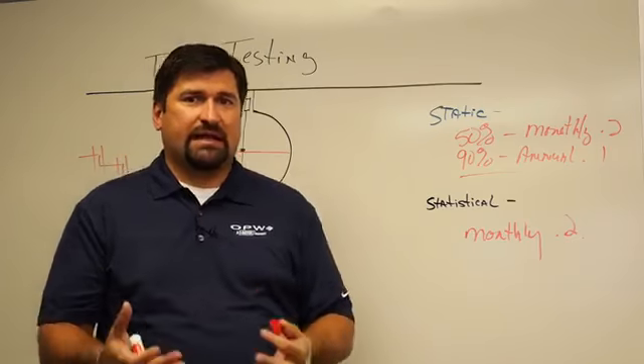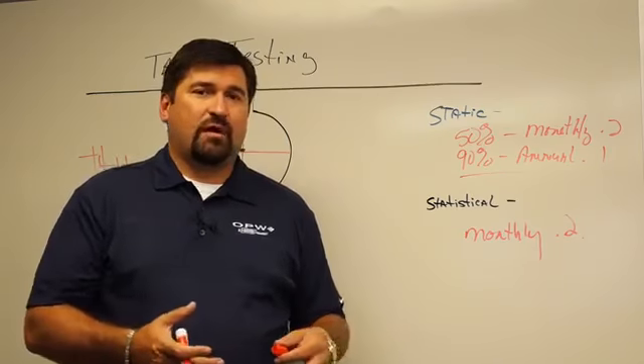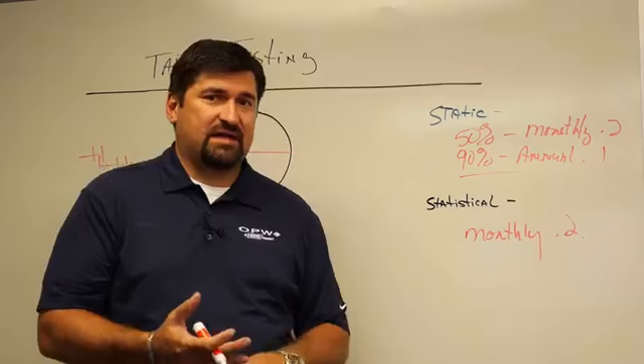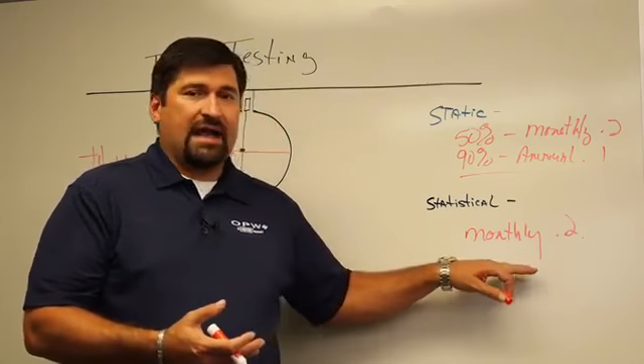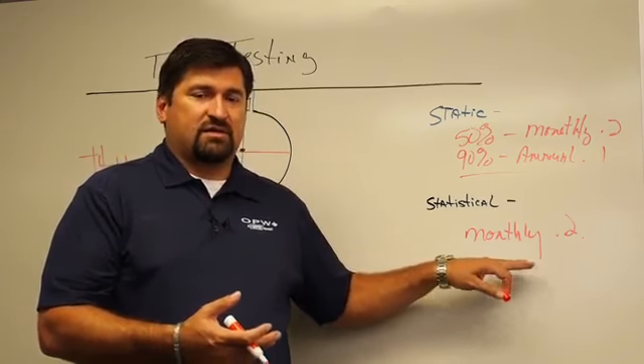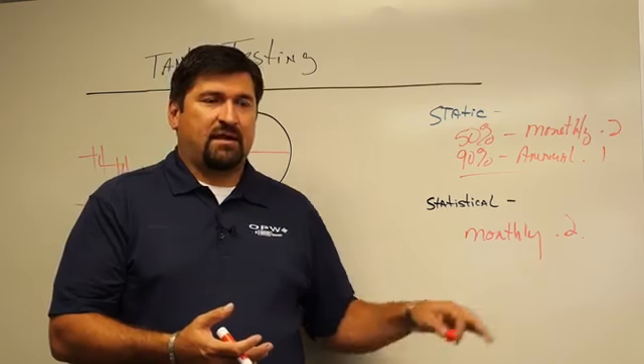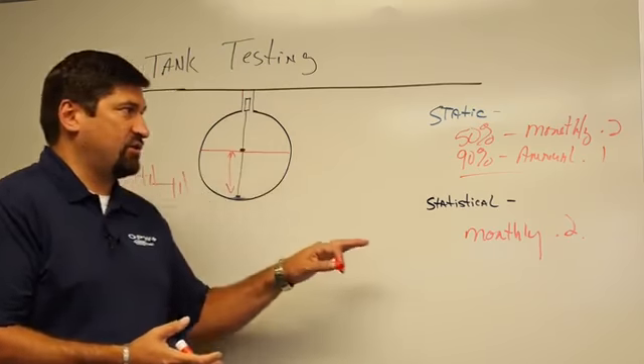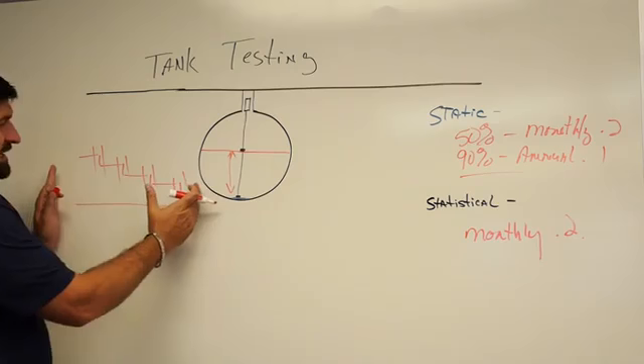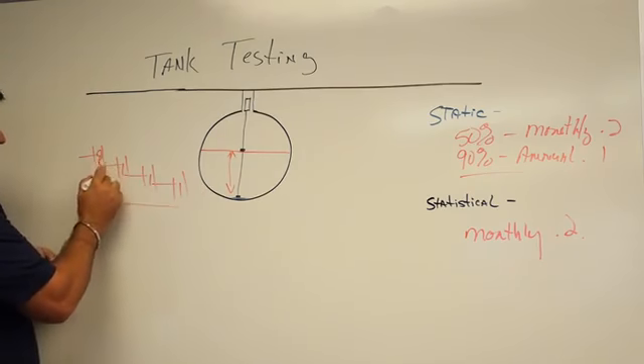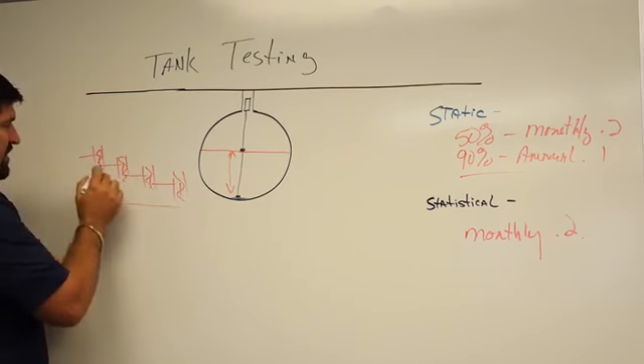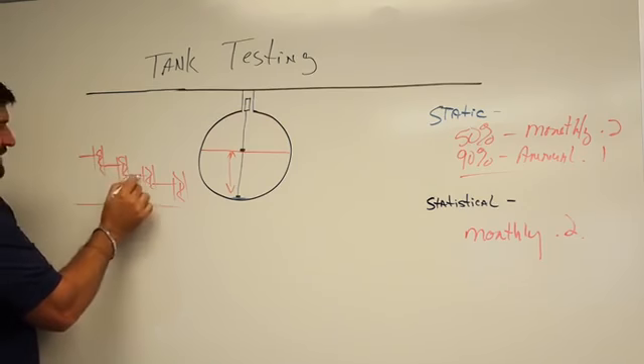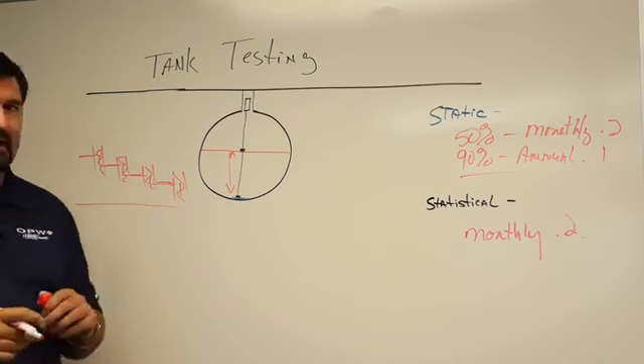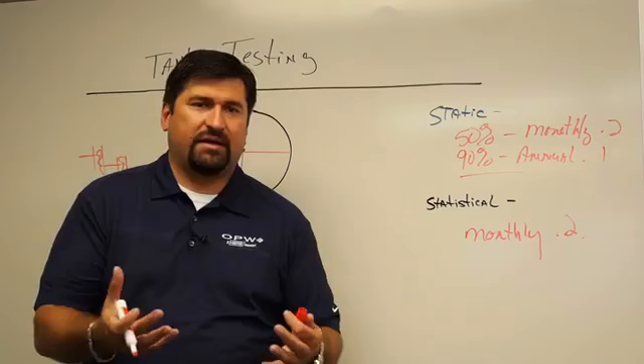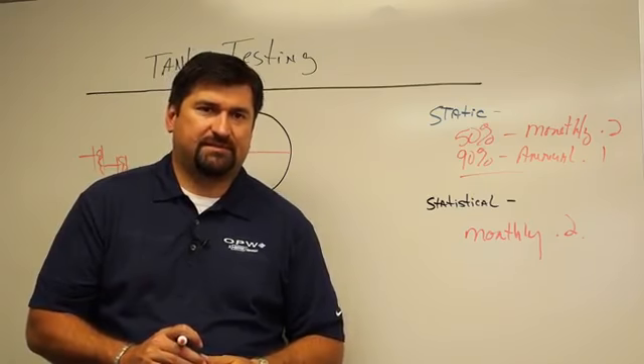But when you're dealing with a retail environment and I'm open 24 hours and I'm pumping constantly, especially sites that are very busy, I don't want to have to take this tank out of service. So they'll go ahead and run a statistical test, but at that point you're basically just doing a static test, taking your dispensing cycles, cutting these sections off, and only highlighting the sections of quiet time, adding them together to create a static 0.2 test.